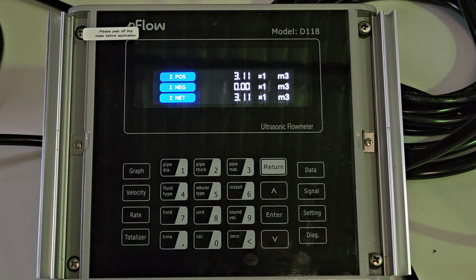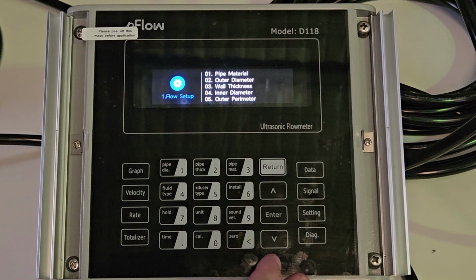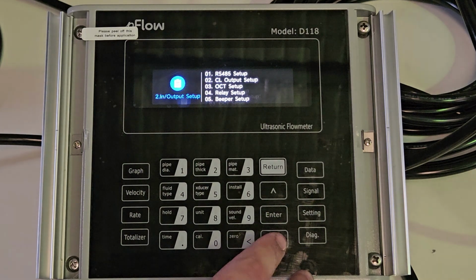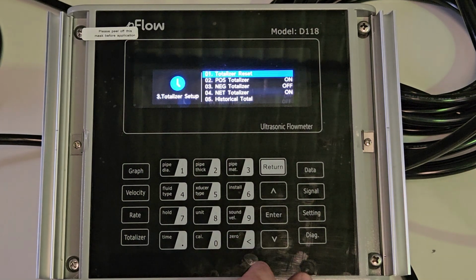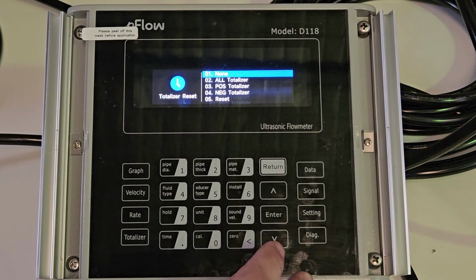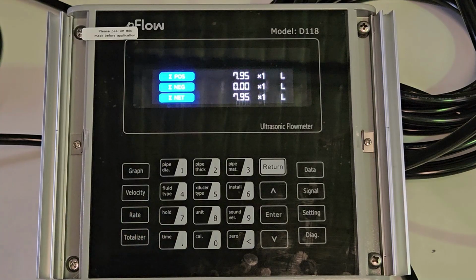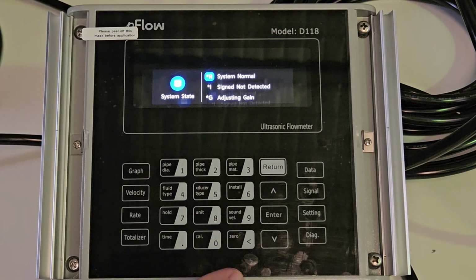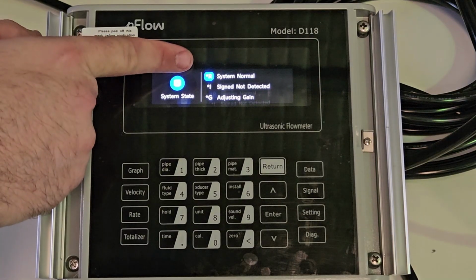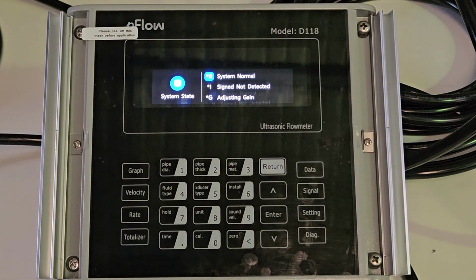If you want to reset the totalizer, press the setting key, scroll down to totalizer setup, then press enter. While highlighted on totalizer reset, press enter again. You can choose to reset all totalizers or just one at a time. Now we can see the totalizer reset back to 0 and is gradually increasing with flow. A useful place to check for any errors can be found in the diag shortcut. Here we have system normal shown.